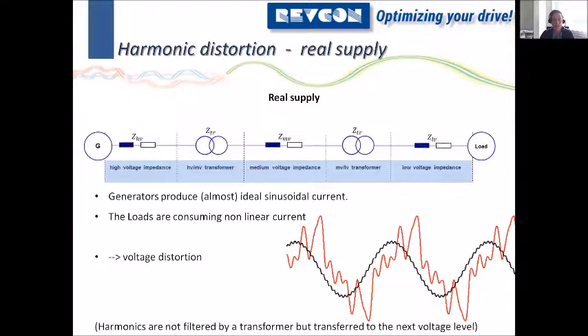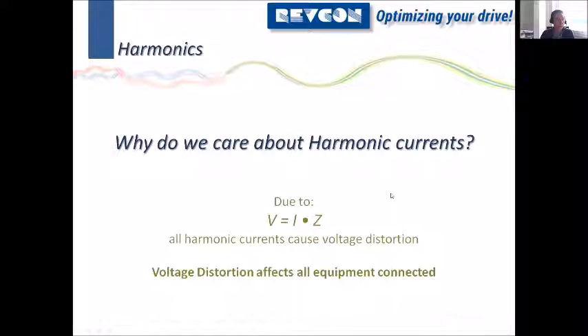So basically, we don't really care about the harmonic current. All equipment, or at least equipment that will cause harmonics, is sized to cover these harmonic currents. So the currents are not the problem. The resulting voltage from this current is the problem, because this voltage will affect all the other equipment connected to the same supply. So that is the real problem. All harmonic currents cause voltage distortion, and voltage distortion affects all equipment connected. To be fair, it affects all equipment except maybe a heating resistor or any very simple device. For example, direct online motors will suffer, drives will suffer if you have high voltage distortion.